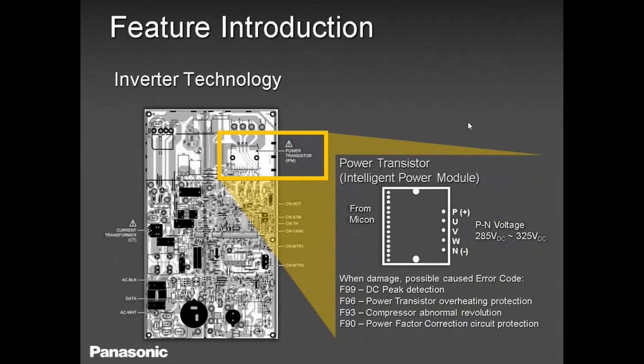So basically what happens is you get your incoming power there, and then it gets converted into DC. And when it gets converted into DC, it goes through this IPM module. That board is responsible for converting the single phase to DC, and then DC to three phase. So here we have three phase coming out to run this compressor.